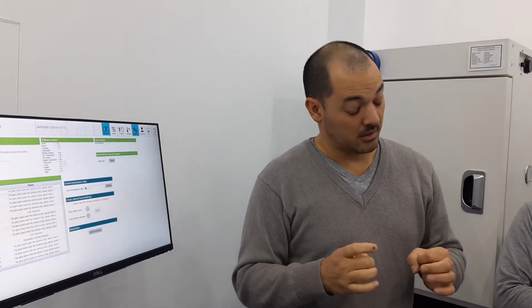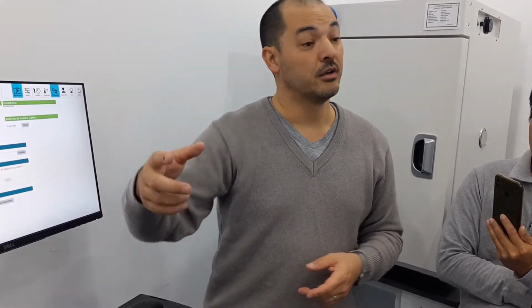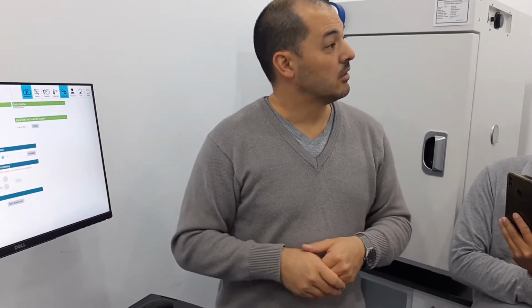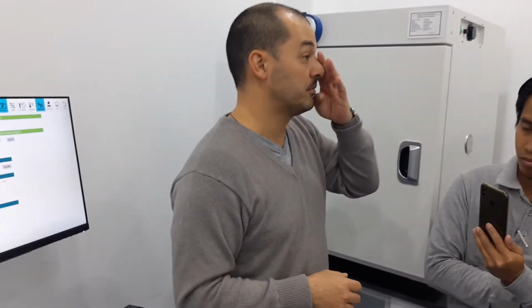But then after, if you have a mold, aerosol contamination of mold, it happens sometimes, and it's quite difficult to get rid of it. Especially, some parts in the machine you cannot have access to. So an incubator, for example, is so simple. You can clean with a wipe everywhere. But this one, there's holes and the machine goes inside and the air goes. So what you can use is, we validated a disinfection process with a small machine you can put inside, which will make like a cloud of H2O2, so hydrogen peroxide.